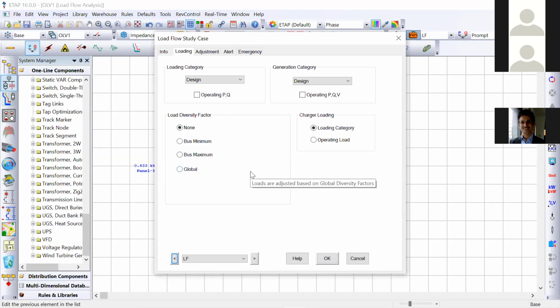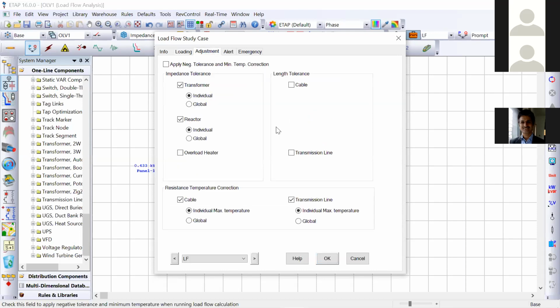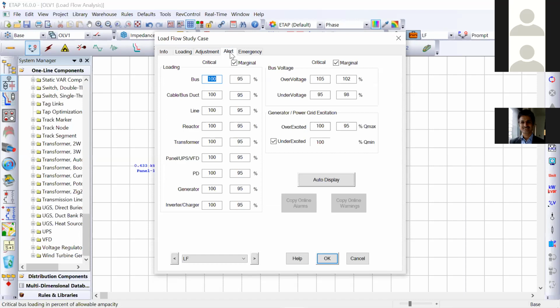We are going with the highest kilowatt rating of the device. Adjustment: this is basically for individual devices, where the adjustments are being done. Alerts: suppose your bus bar has 5% voltage variation withstanding capacity, then you should mention 95% over here. Similarly, you should mention it for all the devices. Based on these variations, ETAP will perform the load flow calculation and it will initiate errors. Whenever a parameter crosses beyond this range, it will show you an alert or an alarm.